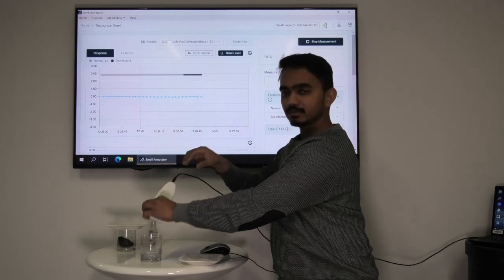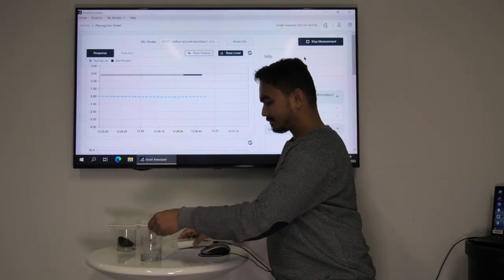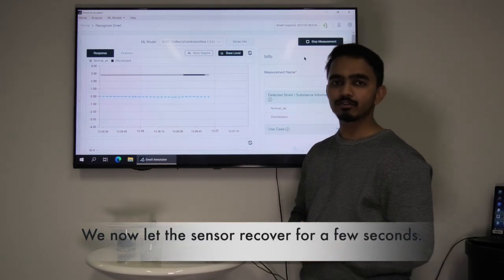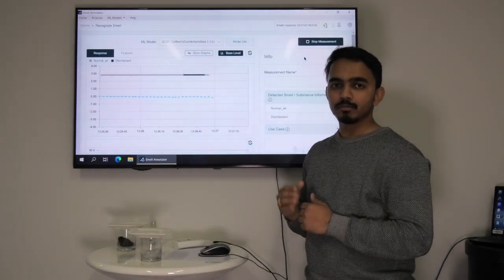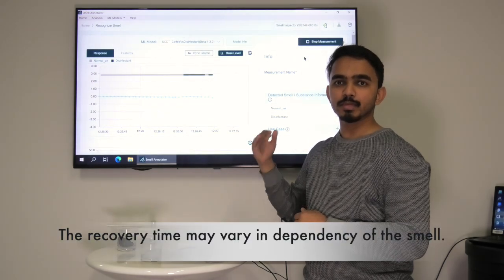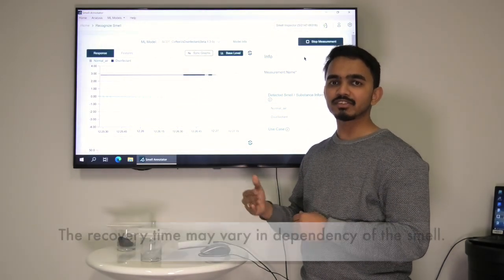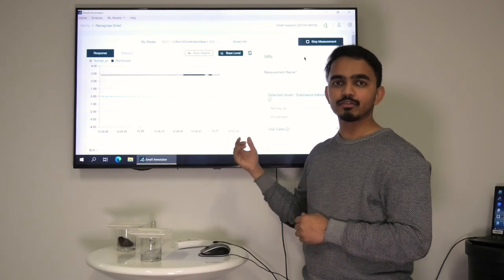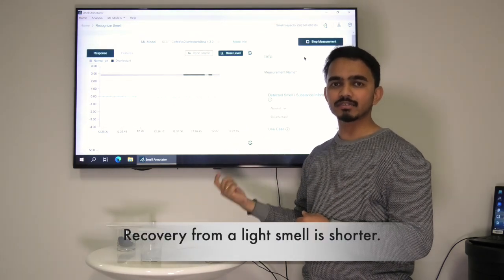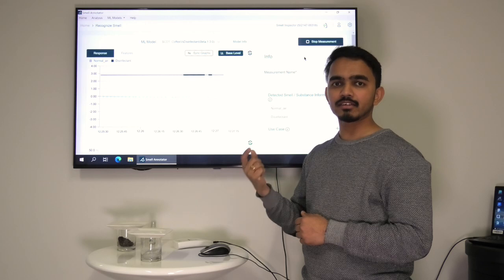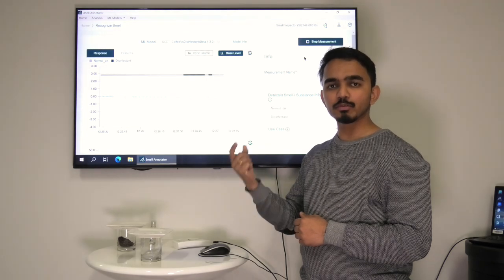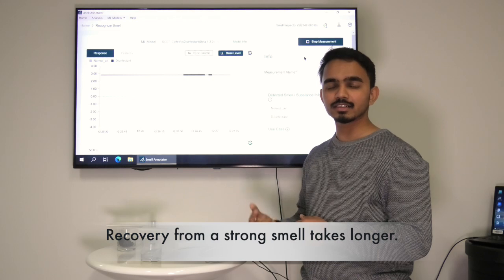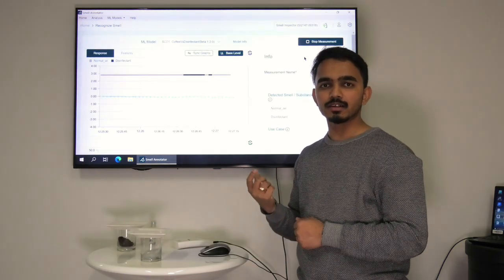Now we will take the device out, cover the glass which contains the disinfectant again, and let the sensor recover for a few seconds. The recovery time may vary in dependency of the smell. For example, if we expose the smell inspector device to a light smell it will take only some seconds to recover. For a strong smell the recovery could take a few minutes.